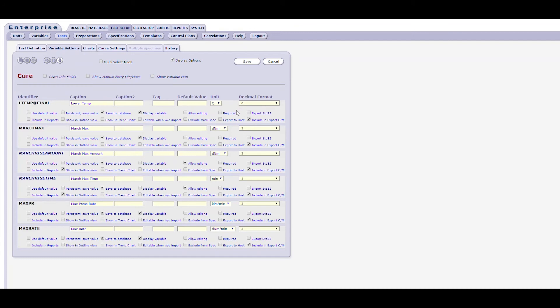The default caption for each variable, as defined in the test setup variables form, can be overridden using the caption field. If the caption is displayed in blue on the form, that indicates the caption matches the default value. A second caption field has been included and works similarly. A possible use for the second caption could include displaying the caption in a second or local language. The tag field is designed for use when certain instrument interfaces are used to exchange test information with an instrument. The default value field should be used to set a default value for the given variable, and is useful for temperature and time set points, among other things. For many variables, leaving this field blank may be desirable.